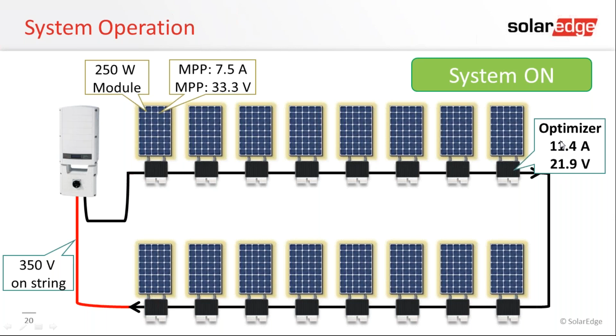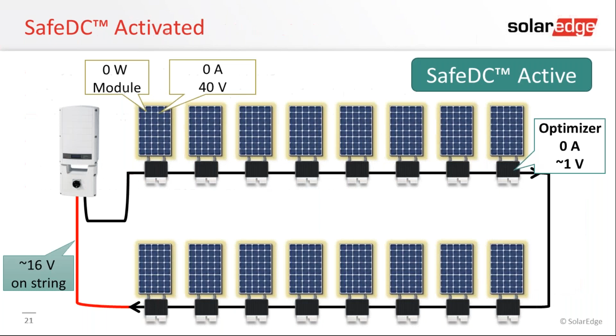So let's look at what the system's doing. The system's on. Optimizers are at 11.4 amps, 21.9 volts. Once we initiate our rapid shutdown device, the optimizers within 30 seconds revert to 1 volt per optimizer and 0 amps. And we basically do this over DC power line communication, and it's a high frequency signal that we use to help us do that. Did that answer your question? Yeah, that walks through the process.